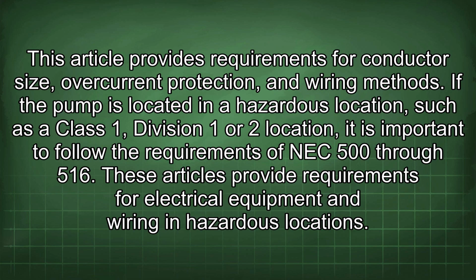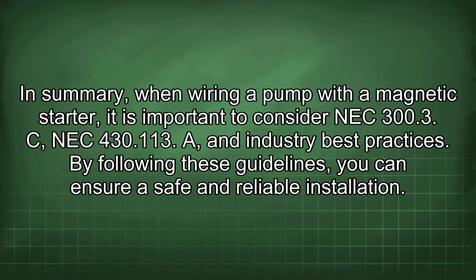If the pump is located in a hazardous location, such as a Class 1, Division 1 or 2 location, it is important to follow the requirements of NEC 500 through 516. These articles provide requirements for electrical equipment and wiring in hazardous locations. In summary, when wiring a pump with a magnetic starter, it is important to consider NEC 300.3(C), NEC 430.113(A), and industry best practices. By following these guidelines, you can ensure a safe and reliable installation.